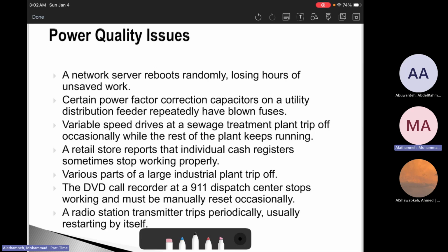The other scenario is capacitor fuses blowing repeatedly. This can happen because of the transients during switching. The transients of the capacitor switching can cause a resonance with harmonics, or an incorrect capacitor bank design can make it work at the resonance frequency, which can magnify the harmonic current to a very large value. As a result, the fuse will blow out. So the fuse blowing repeatedly can cause a problem.